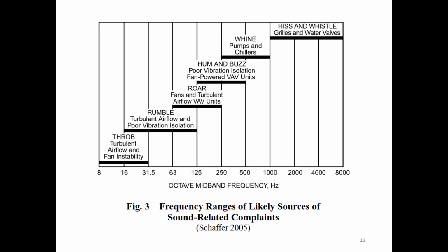This slide shows frequency ranges of likely sources of sound-related complaints. If someone in a space is going to complain about really low frequency noise, it's probably the throb of turbulent airflow and fan instability, like an unbalanced fan that's driving into the ground every time it rotates, causing vibration throughout the building.